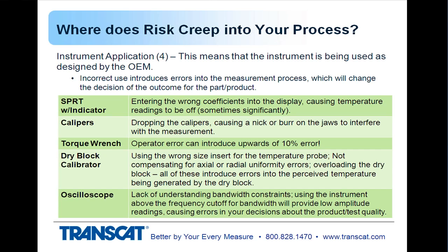Torque wrenches. Without having any damage to the instrument at all in its normal use, there's enough influence from how the operator uses a torque wrench that you can introduce up to 10% error in the reading. And a good gauge repeatability and reliability study would indicate how much error you have.